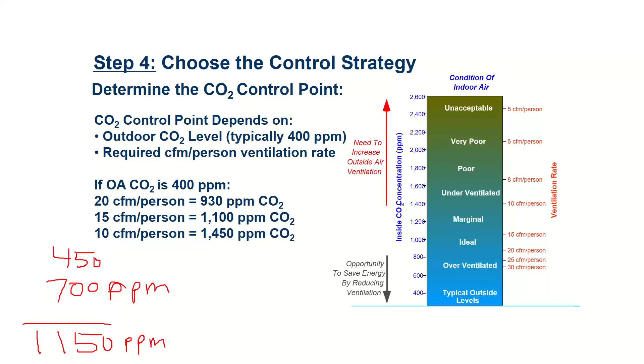If I was in some rural place, maybe it's like 400. So now my set point's 1100. If I was in a densely occupied, urban downtown area, maybe it's 500. But it's going to be something similar to that. So 1100 to 1200 is going to be my set point for most of these buildings. That's going to be a pretty common spot.